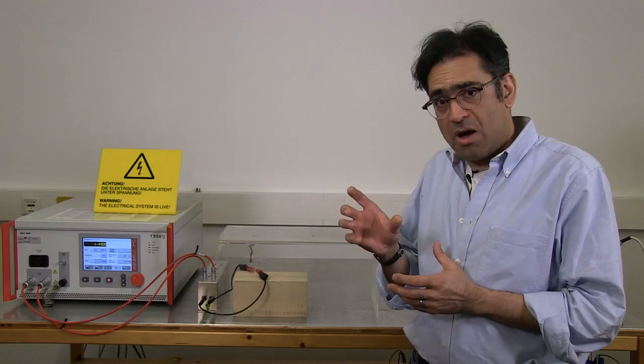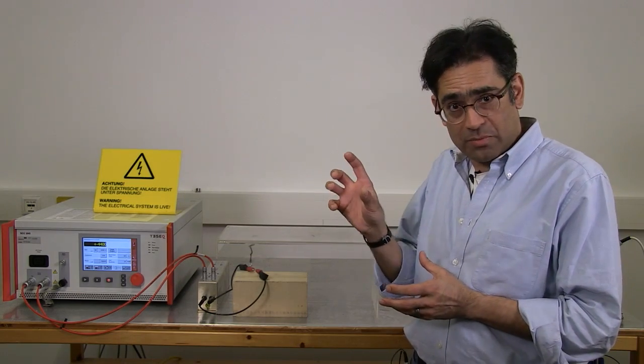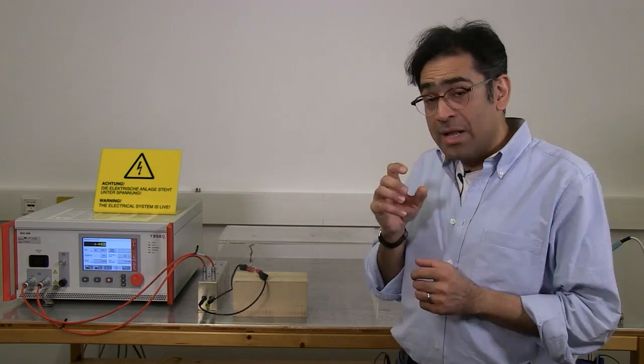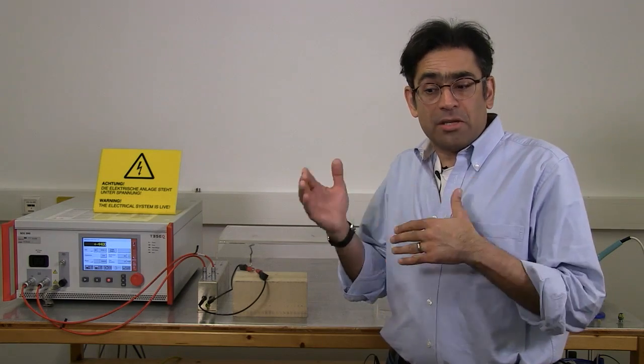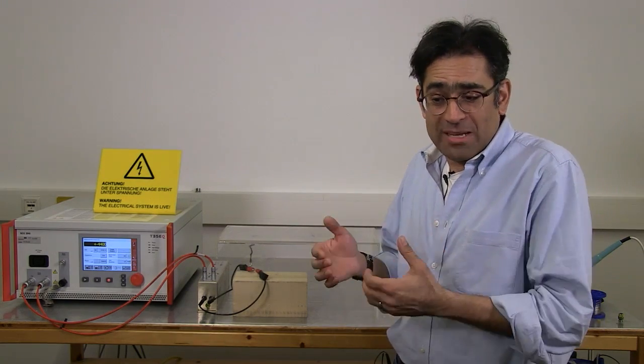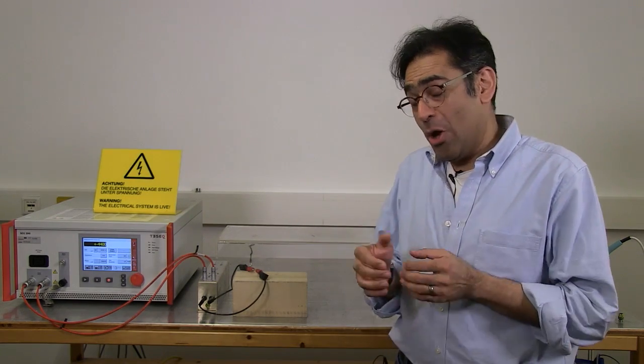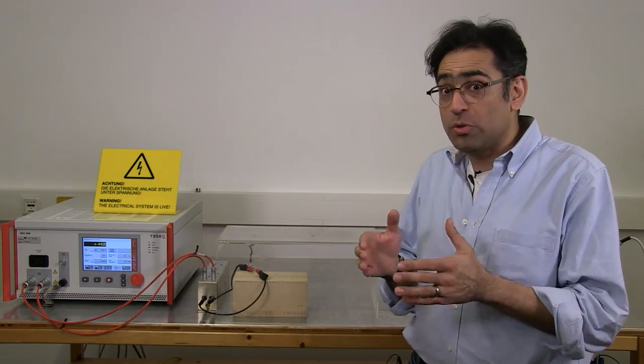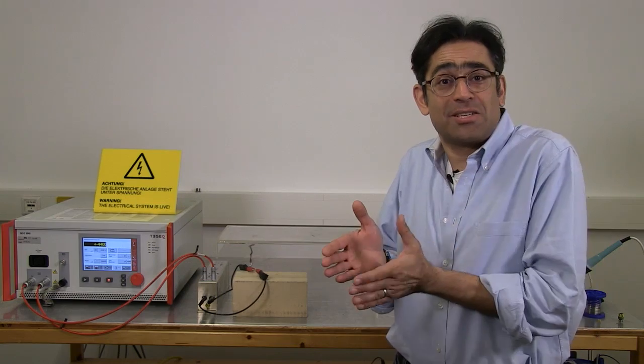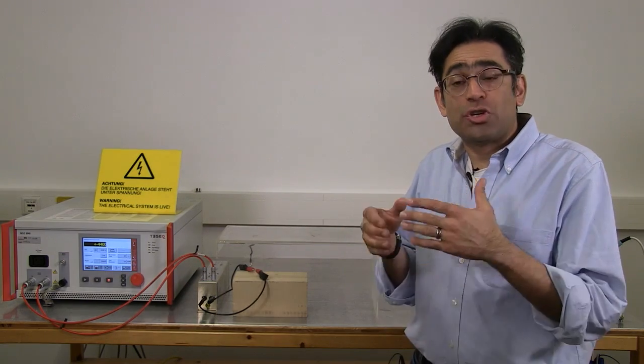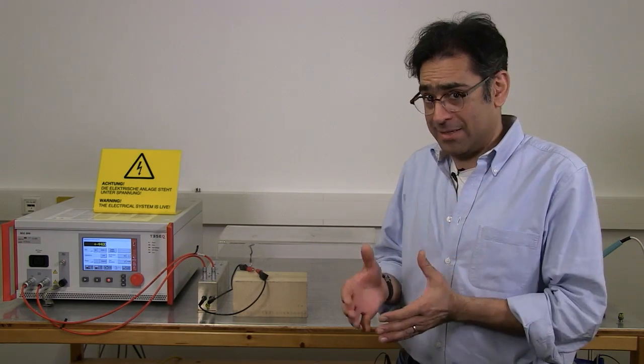On a device that has got a pluggable power supply, the surge test is usually applied to the power supply that you plug into the wall. Now instead of showing you the surge test on just a power supply which will not be terribly interesting, what we are going to show you is what happens if you perhaps use the wrong type of capacitors inside of your power supply which are not designed to withstand the surge test.